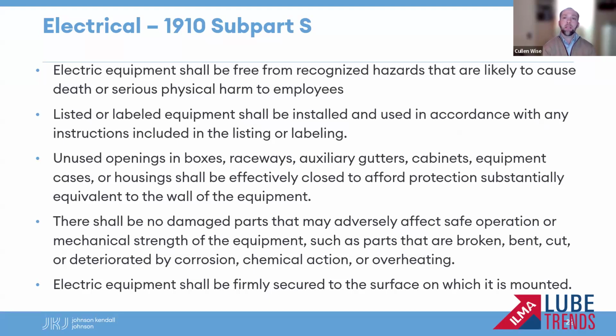Next, we have listed or labeled equipment shall be installed and used in accordance with any instructions included in the listing or labeling. So this one's a little bit more vague, I guess. Probably something that a lot of folks aren't really familiar with. What does listed and labeled mean? Listed and labeled means that a nationally recognized testing laboratory, or NRTL, has done performance testing for equipment, and then they've listed and labeled it as use in a specific manner, right, for an intended purpose. Underwriters Laboratories, UL, is probably the most commonly known one. They are one of the NRTLs. There are certainly others, but UL is again the most common one. So UL tests components and equipment to certain specifications, asking how they are performing. Yes, we've met a performance specification. It should be used in this certain manner, right?